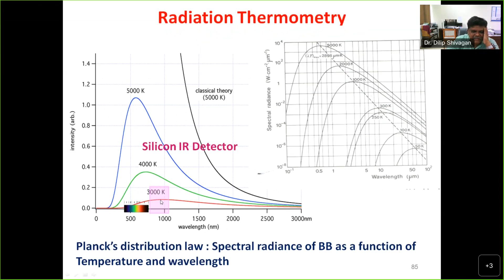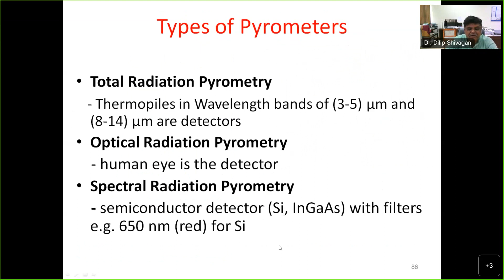So there are total radiation thermometers, optical thermometers, and spectral radiation thermometers. The difference is only in the spectral part. Out of this black body band, you select the wavelength. As temperature increases, its intensity will keep on increasing, because it is not 100% quantum efficiency for all wavelengths that you receive. So silicon or InGaAs type detectors are used with red wavelength. For our pyrometer, it is a silicon detector, and we have 650 nanometer.